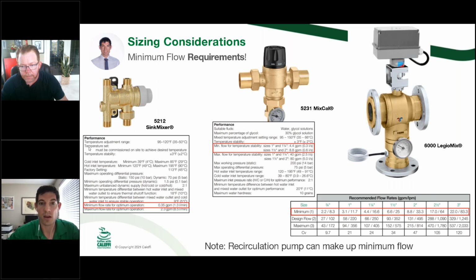So in the middle there, that Thermostatic 5231 MixCal, the minimum flow rate is as low as 4.4. And then the difference with the LegioMix is it actually can go really low because it's a single ball valve that can close really tight. So one of the big differences in thermostatic and electronic with a ball actuating the flow with the LegioMix is that it can close completely the hot, and it can open just a crack, where with thermostatic mixing valves, they have a cartridge that's going to slide up and down, and you might have 90% hot and 10% cold, or vice versa, but they don't generally, except for a couple exceptions, close one or the other hot or cold completely. They're not really meant to do that. But a valve like the Legiomix can do that, and it's the reason you can get to a smaller minimum flow rate too. So those are a couple little things.